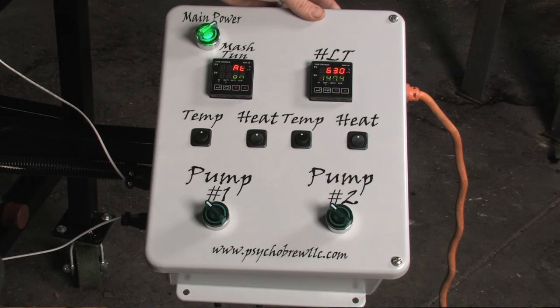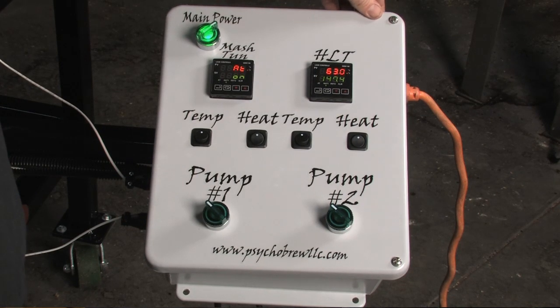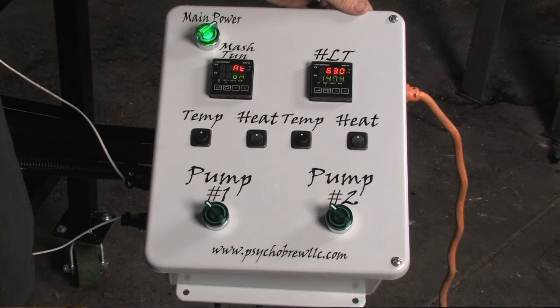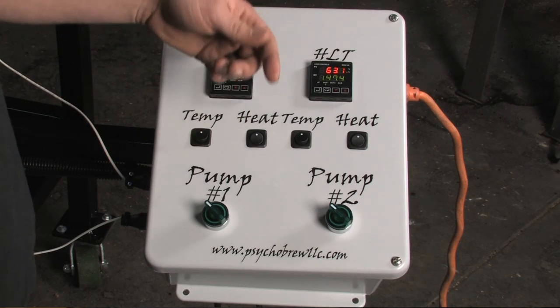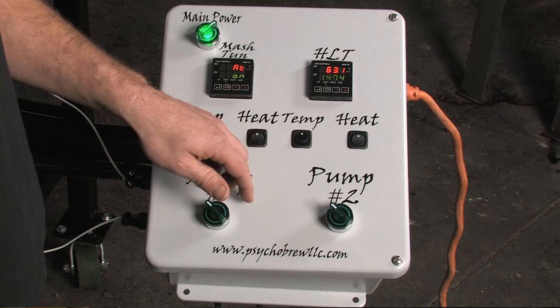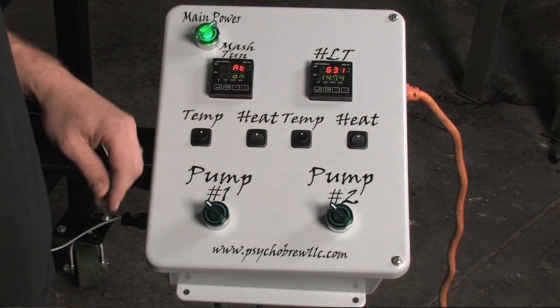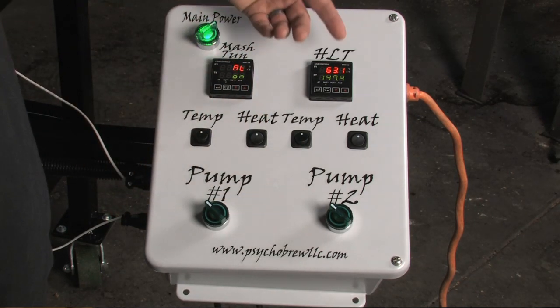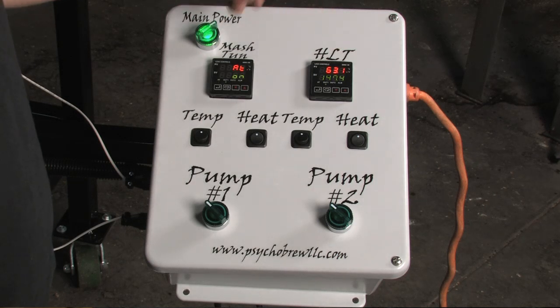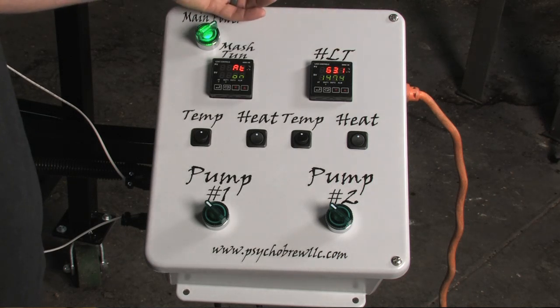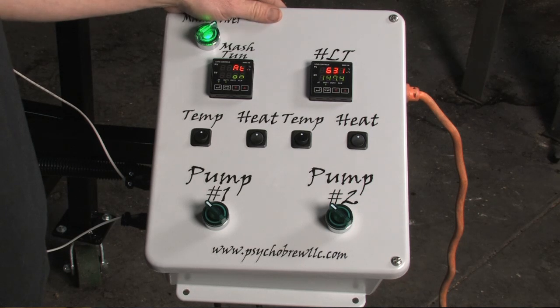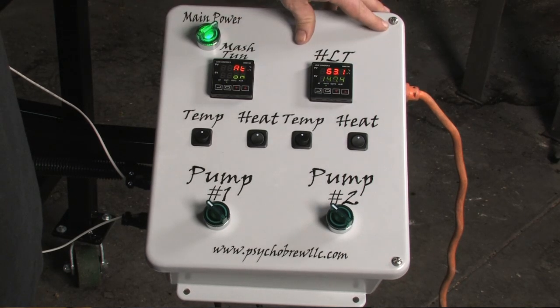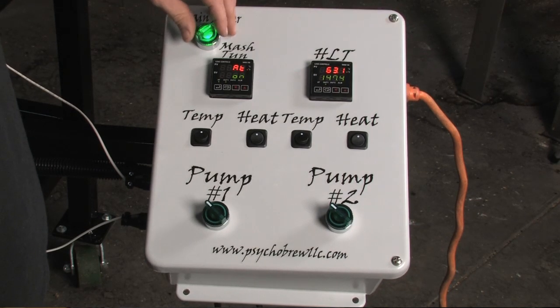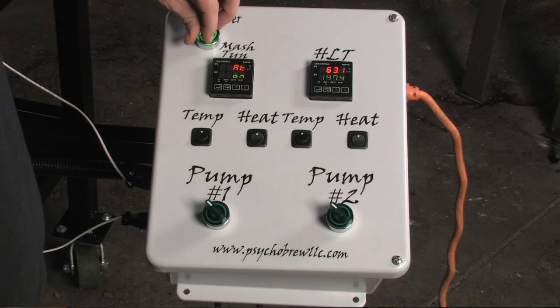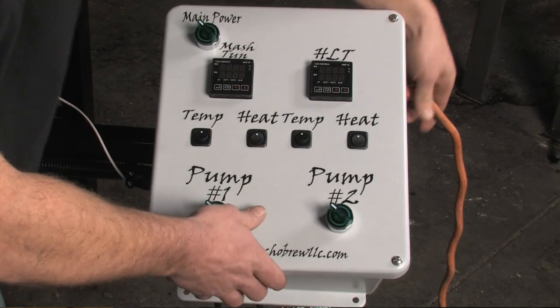If for some reason you have a controller not function, or you have a burner not light, it doesn't appear to be getting power, there are breakers inside the panel for low voltage. You have 2 voltages inside here. You have 120 volt that's supplied by the cord, and then you also have a transformer to power up low voltage, 24 volt, to power up the gas valves and ignition modules.